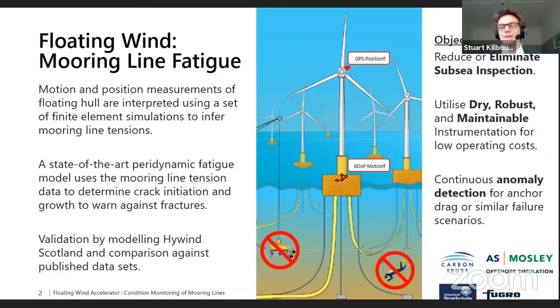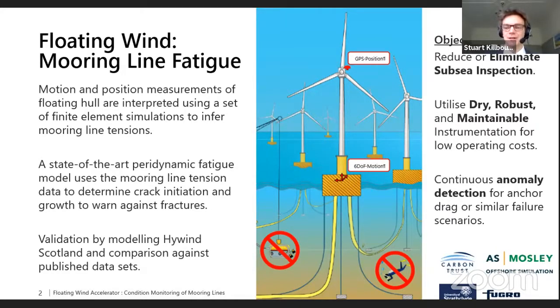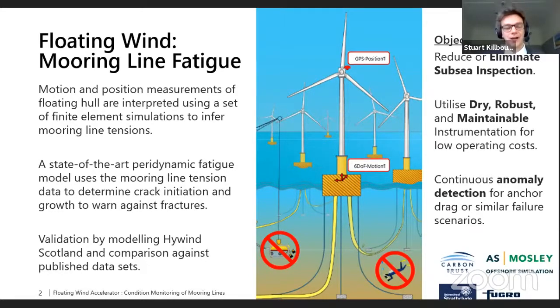The objectives of the project are to reduce or eliminate subsea inspection of the mooring lines — one of the key critical cost-saving objectives — achieved using remote monitoring with reliable and robust instrumentation within the floating hull in a protected environment. Because we're making measurements on a continuous 24/7 basis, we can perform anomaly detection on the data and identify in a timely manner concerns or failure scenarios such as anchor drag.